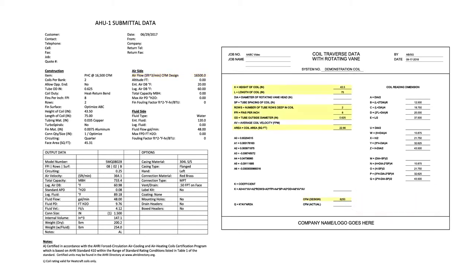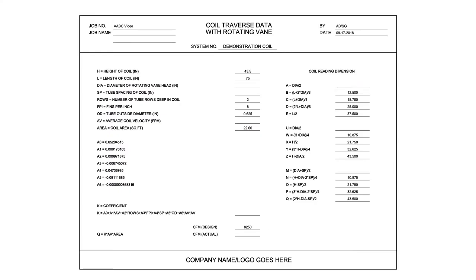The coil traverse data with rotating vane form has been populated with the AHU-1 submittal data. Next is to verify the submittal data while in the field and to complete the form by measuring the diameter of the rotating vane head and tube spacing of the coil. Then the coil reading dimension data on the right will be automatically calculated, and this data will be used to measure and mark the coil for the standard and offset velocity reading locations.